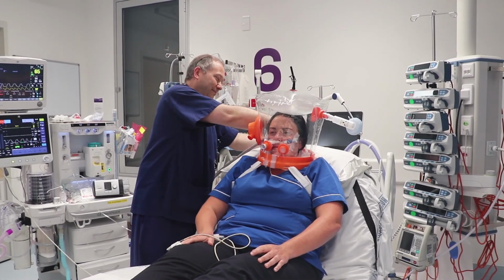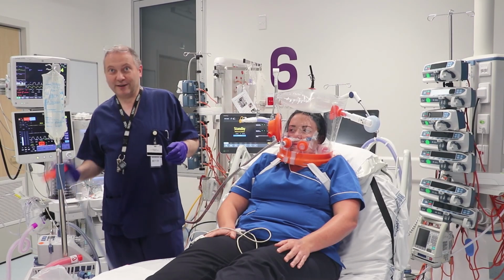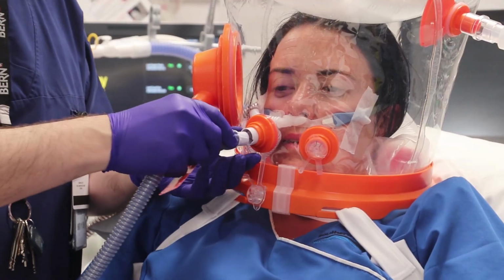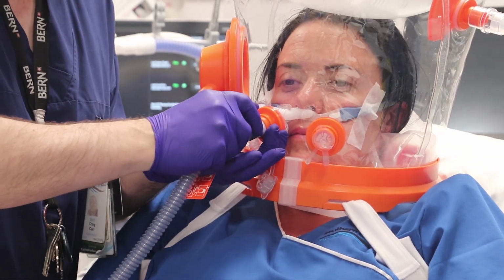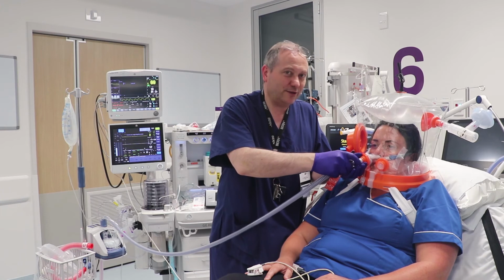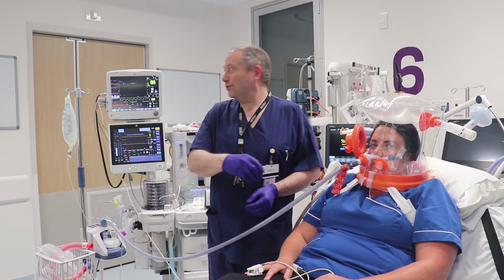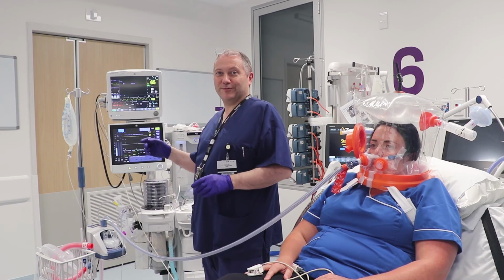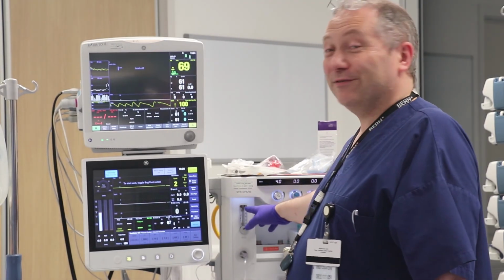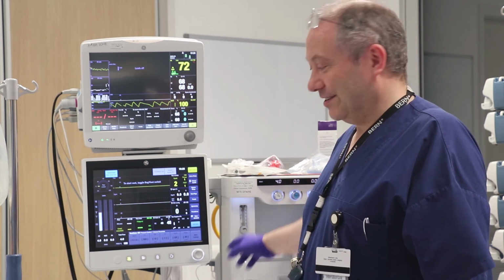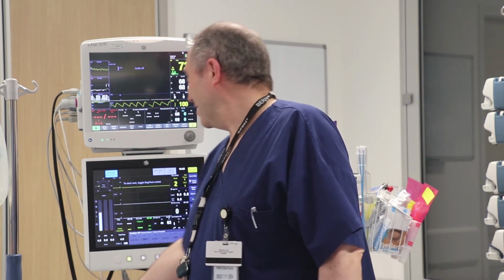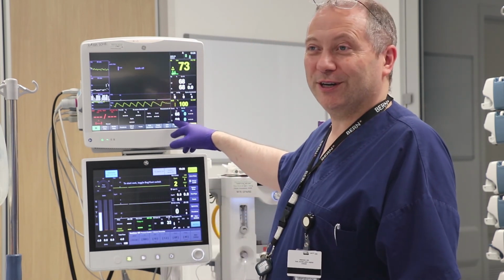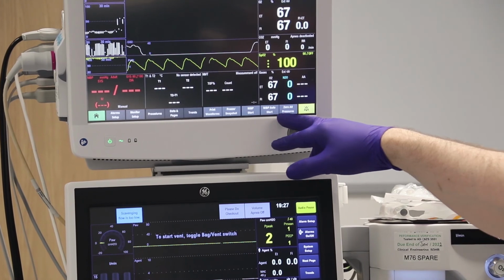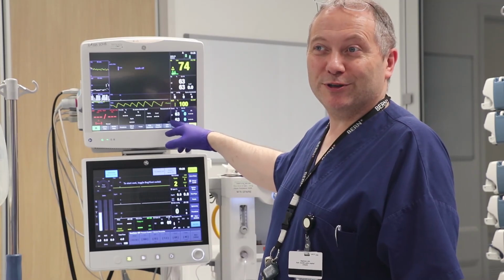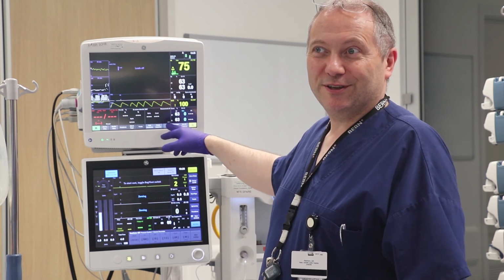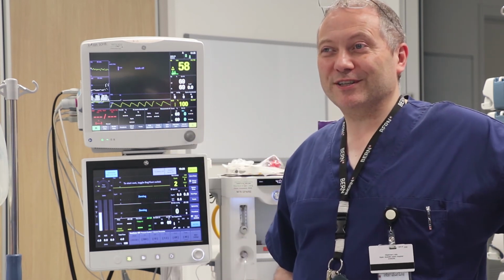And the neck cushion. And now we're going to connect the Airvo to the nasal cannulae. When we connect this, the CO2 will tend to zero. What we can see is with a flow of 15 litres per minute of oxygen via the Airvo, we're actually delivering an FiO2 to Carla of between 60 and 70%. That's more than double the FiO2 we achieved when we were running the same flow of oxygen directly into the helmet.